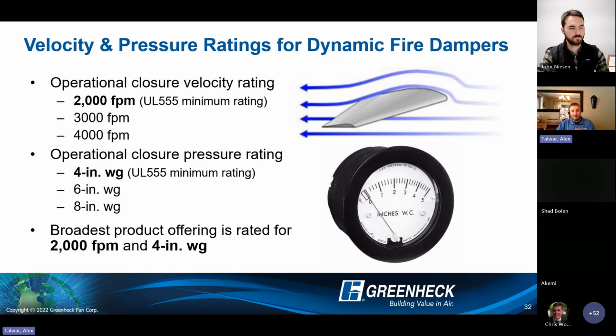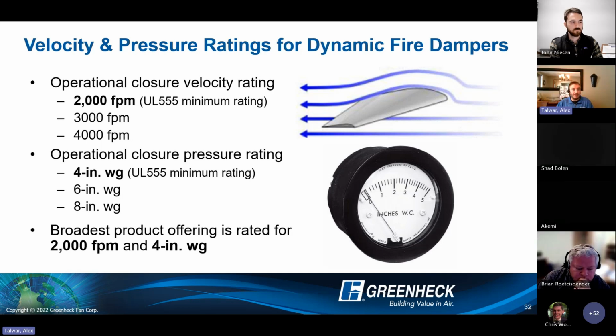You can make your dampers bigger, it's easier to pass the tests. They usually cost less. You can use less material, all that kind of stuff. Of course, there will come a time where you do need those elevated ratings, 3,000 feet per minute velocities, things like that. But just be aware that once you start bumping up in the velocity and pressure ratings, it will limit you in terms of the maximum allowable sizes of the products and things like that. So just a word of caution on that.